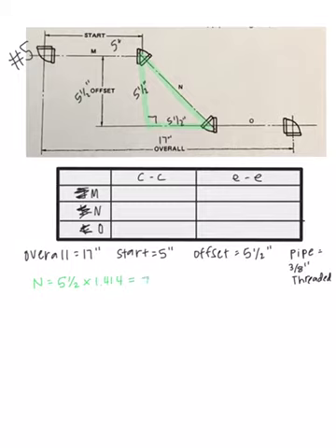And I'm getting 7.777. Now, I have no idea what 0.777 is as a fraction. So in the back of my book, data table 1, I'm looking for 0.777, and it's about 3/4. So pipe N is 7 3/4 from center to center of those 45s.